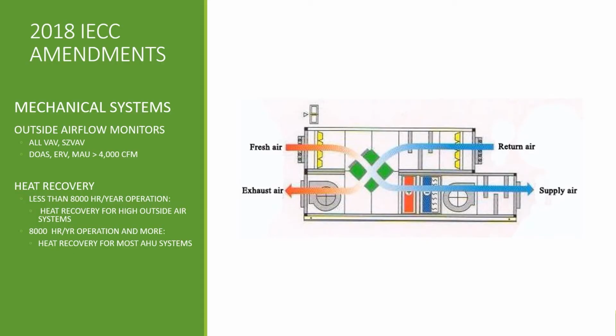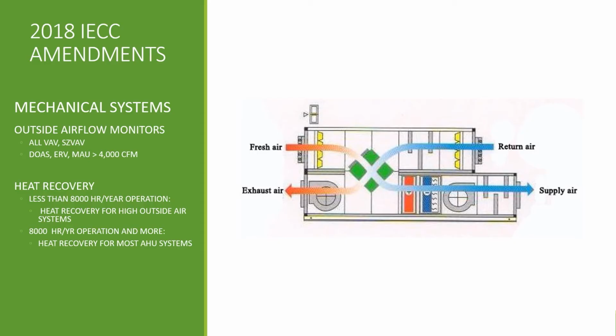Heat recovery is the one main thing that Denver has added to the mechanical code. Essentially, for a high percentage of outside air, I want to say 70% outside air and above on a standard building, you're going to have a heat recovery unit. And if you're running a building that's 24/7, you're going to have heat recovery on it as well. So hospitals, but that also means residential, right? Because you're always maintaining ventilation within a residential building as well.